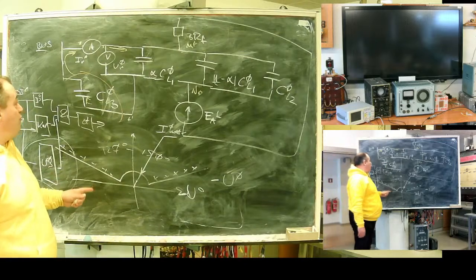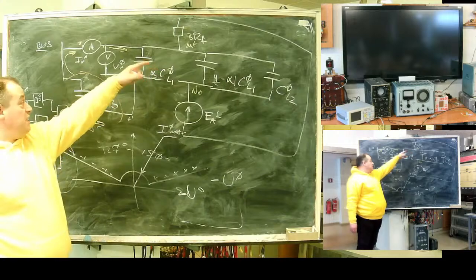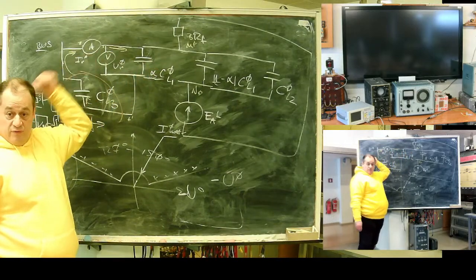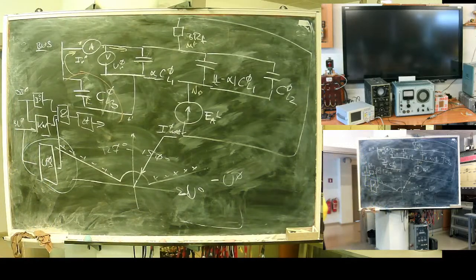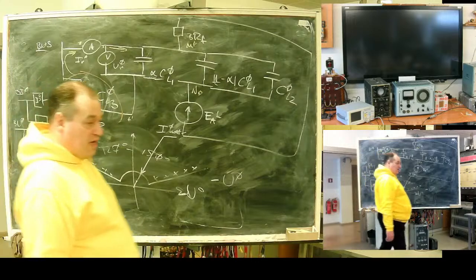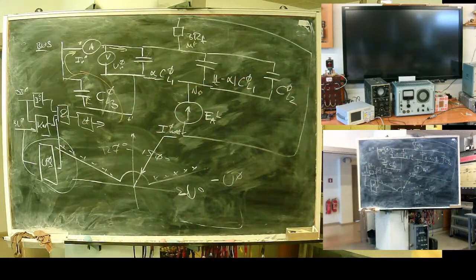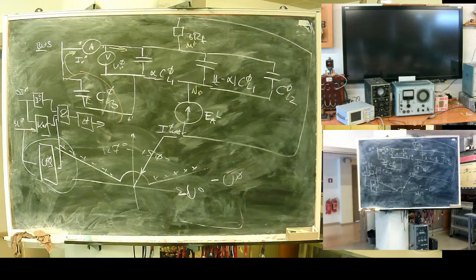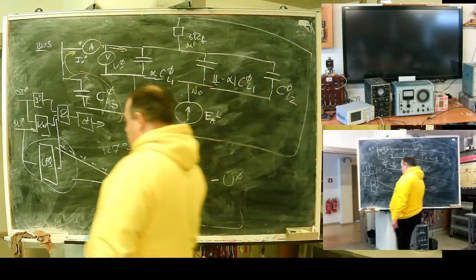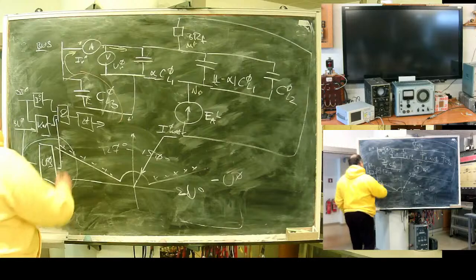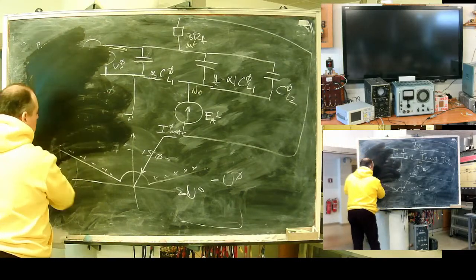In case of internal fault, capacitive current flows like this. In case of external fault, capacitive current will flow this way. And this is it. You cannot use current magnitude to create selectivity. Only direction. To separate, or say segregate, faulted line from health, the only thing you can rely on is a flow, direction of current flow. Current magnitude here, worthless.